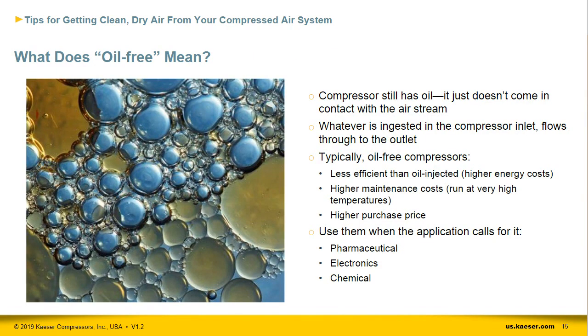So what does it mean to have an oil-free compressor? It doesn't mean that there's no oil in the compressor. It means that the oil doesn't come in contact with the airstream in normal operation. Keep in mind, whatever's in the ambient air is still going to be ingested into that compressor inlet and then flow through the compressor. Therefore, filtration and drying are still necessary for clean, dry air, even in oil-free systems.